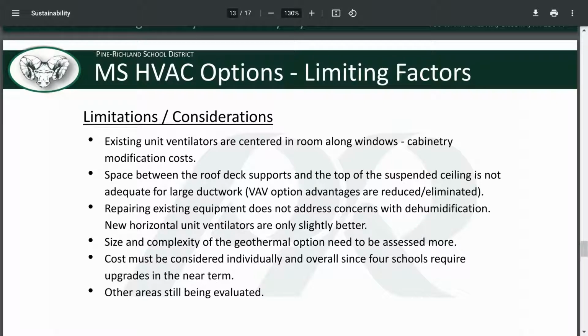The space between the bottom of the roof deck and the top of the finished ceiling really doesn't support the VAV option. The VAV option is made for buildings like Eden Hall, where we can put 10 or 15 units in the whole school and share ductwork for a whole wing, with ductwork feeding all the rooms. To do that you need a lot of space for ductwork, and we just don't have that here. If we tried it at the middle school, we'd have to scale the units down small enough to feed like 2 rooms, which is kind of inefficient.